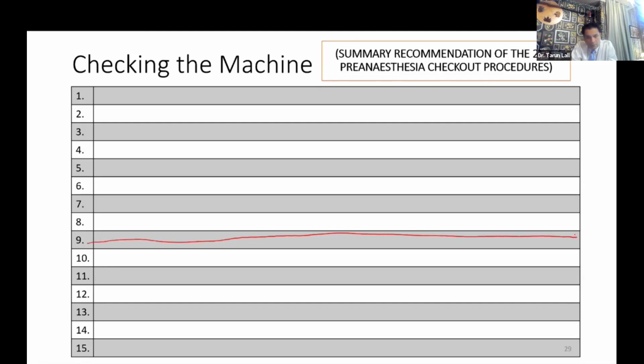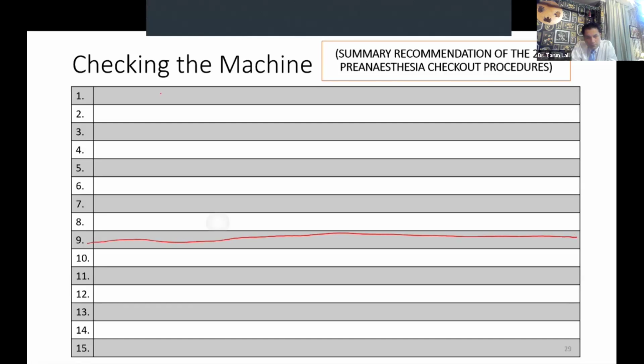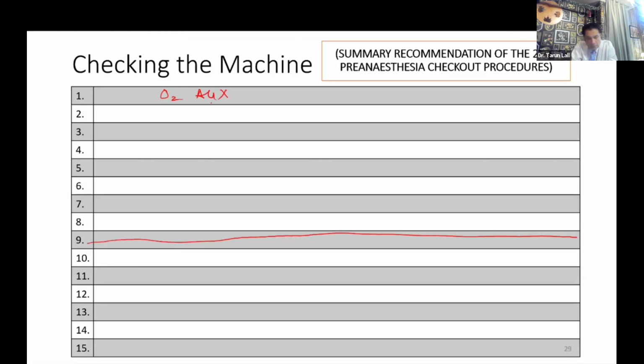So the first 2 points are before I have even touched the machine. The first point is auxiliary oxygen. And this auxiliary oxygen is not the cylinder which is behind your machine. This auxiliary oxygen is another oxygen cylinder with its own valve, with its own breathing circuit, which can be used in case your machine totally fails.